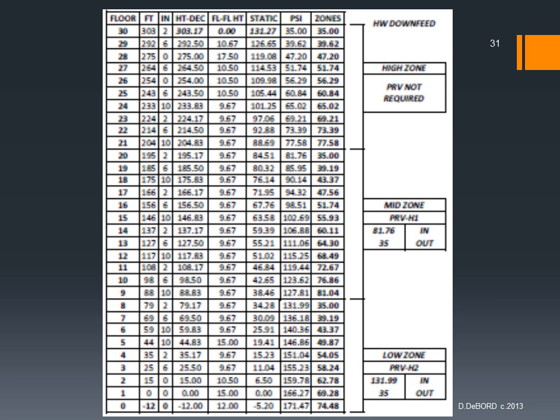This is a spreadsheet that I made. I call it a zone map. It gives me the opportunity to put in the heights, and I can have it calculate the floor-to-floor heights and the static pressures, and then I can look at each zone. I can see if I'm upfeeding or downfeeding, what kind of pressure I'm getting, and also what my PRVs are seeing, what pressure is in, what pressure is out.